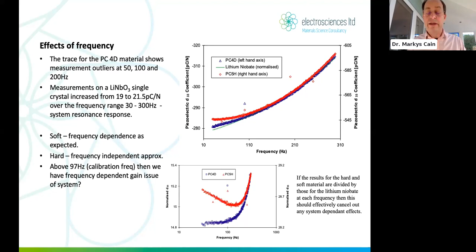Sample geometries. This method is meant to be sample independent. It's geometry independent. You should be able to put thin discs in and big long bars. But the bottom line is it's not quite sample independent, geometry independent. And there is a difference between soft and hard materials. We have an alignment issue. We also have considerable clamping issues. And I'll talk about that in just 1 or 2 slides' time.